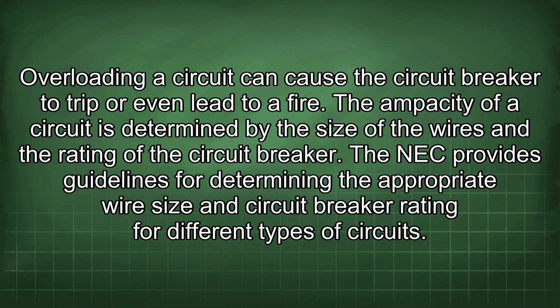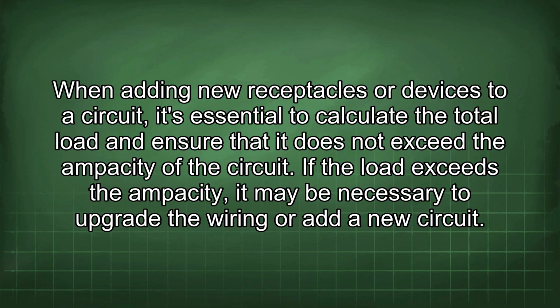The NEC provides guidelines for determining the appropriate wire size and circuit breaker rating for different types of circuits. When adding new receptacles or devices to a circuit, it's essential to calculate the total load and ensure that it does not exceed the ampacity of the circuit. If the load exceeds the ampacity, it may be necessary to upgrade the wiring or add a new circuit.